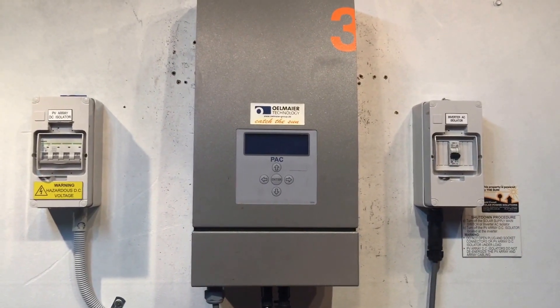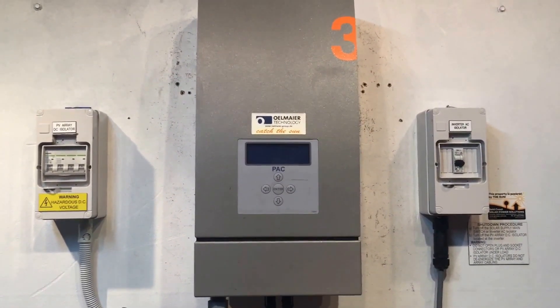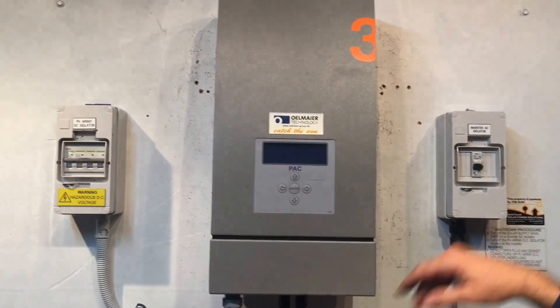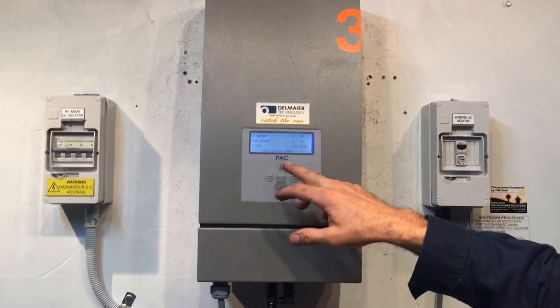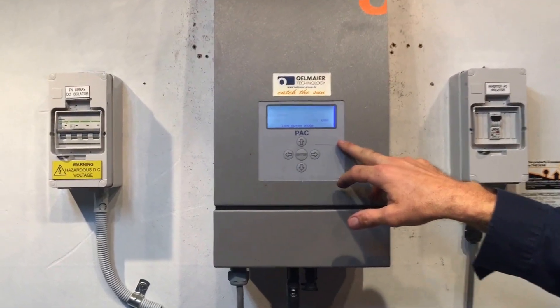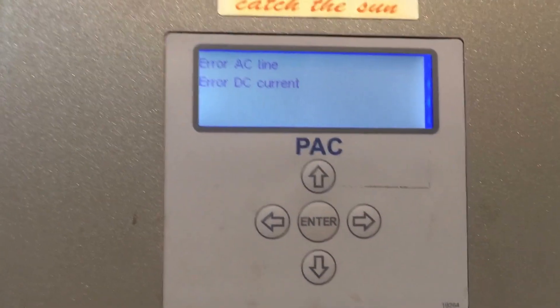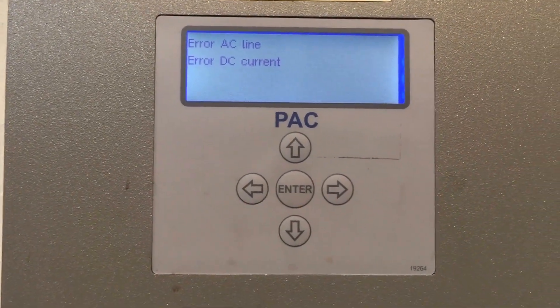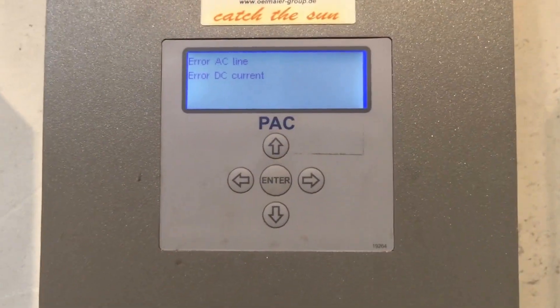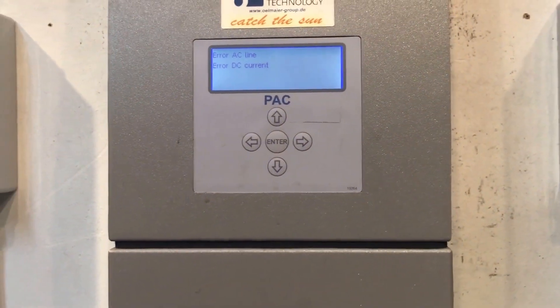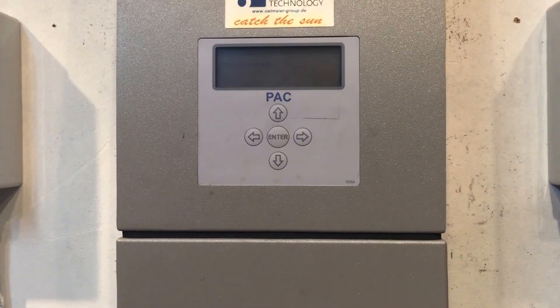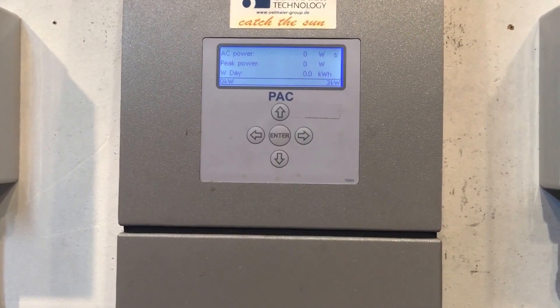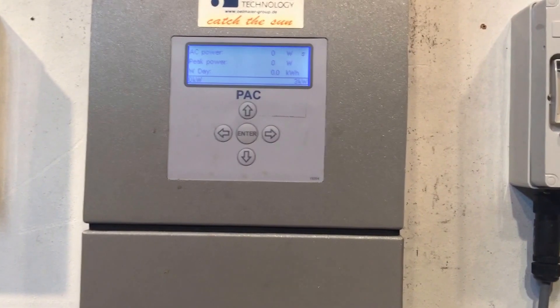The startup procedure is nowhere near as important as the shutdown procedure — just make sure you turn everything back on. We put the DC on and then throw the AC back on. This one comes up with a few things on startup: 'Error AC Line' and 'Error DC Current.' I've checked both those things and there's nothing wrong whatsoever — this is an internal problem with the inverter. The errors appear briefly at startup and then go away, being replaced by the main reading.